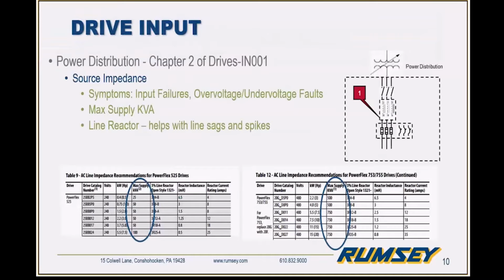Okay, so starting off with the drive input, the first area of consideration with the power distribution, we want to determine the source impedance. If we look at the wiring and grounding recommendations manual, drives IN001, there are tables where we can look up the specific drive type and determine the maximum allowable supply kVA of that transformer.